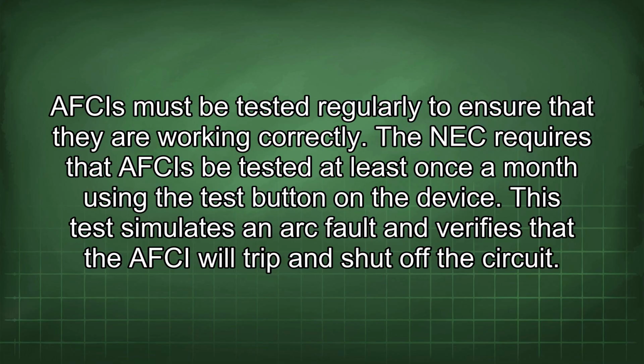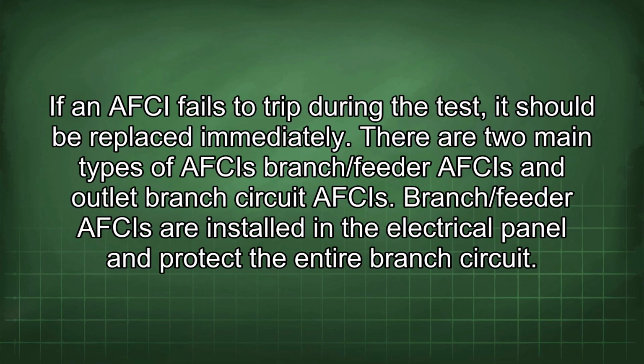AFCIs must be tested regularly to ensure that they are working correctly. The NEC requires that AFCIs be tested at least once a month using the test button on the device. This test simulates an arc fault and verifies that the AFCI will trip and shut off the circuit. If an AFCI fails to trip during the test, it should be replaced immediately.